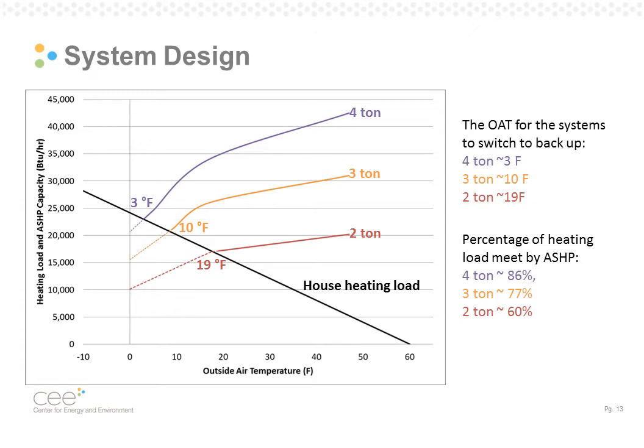So next we'll step into talking about the preliminary results that we have for the study. First, we're going to touch on a few different things, including systems design and furnace integration. So the air source heat pumps were sized for the home's heating load, not the cooling load. This typically meant an increase in tonnage or capacity of the system by 1 size. So where a 2-ton unit would cool a house, a 3-ton unit was installed to meet the heating load. And the purpose of this is to take advantage of the heating capacity at cold temperatures.